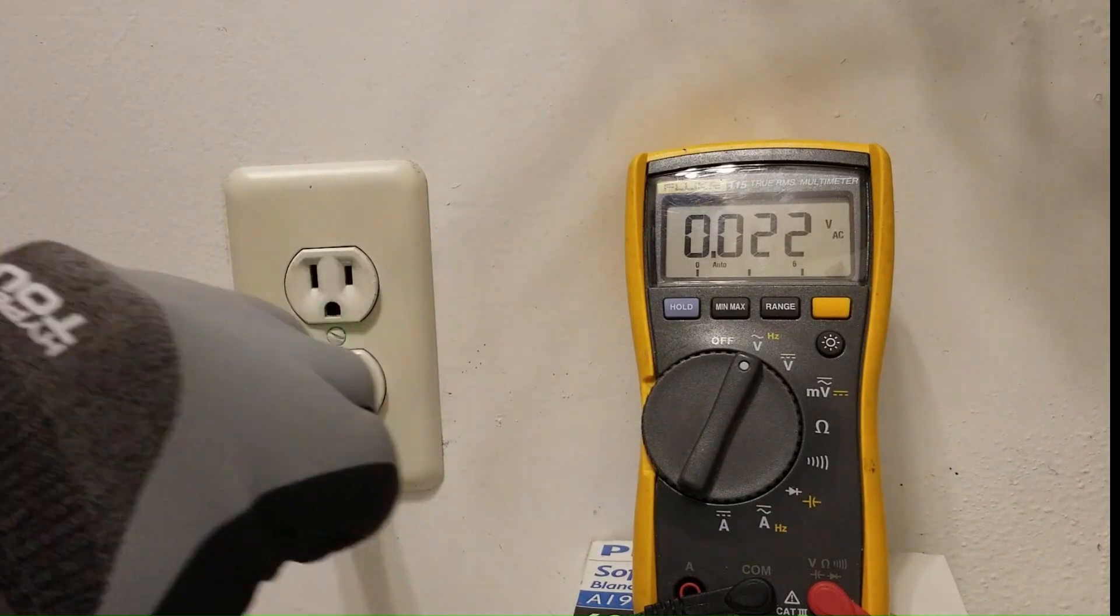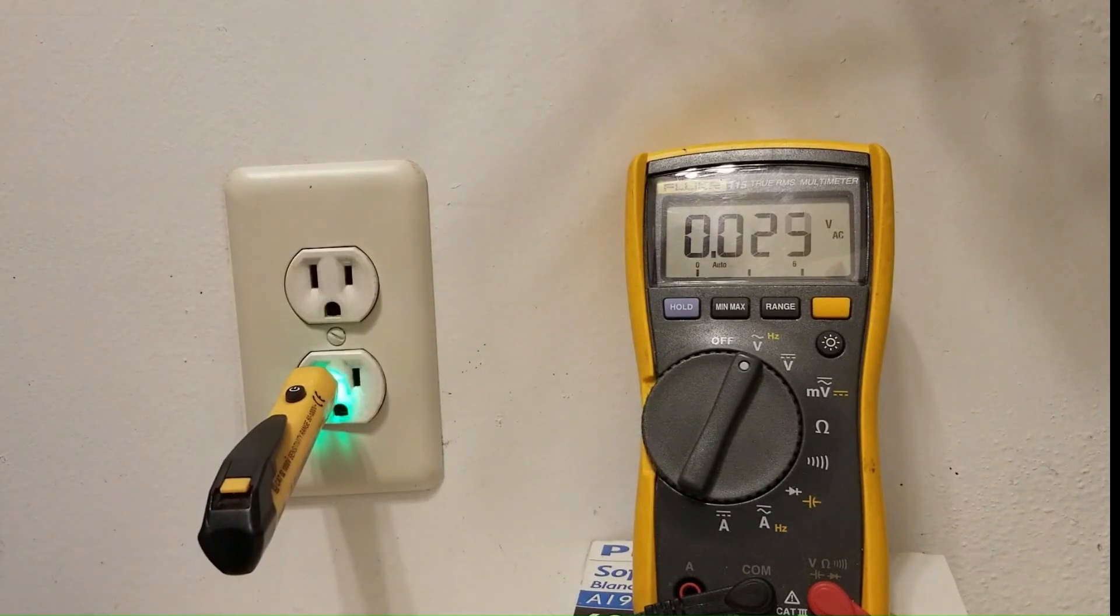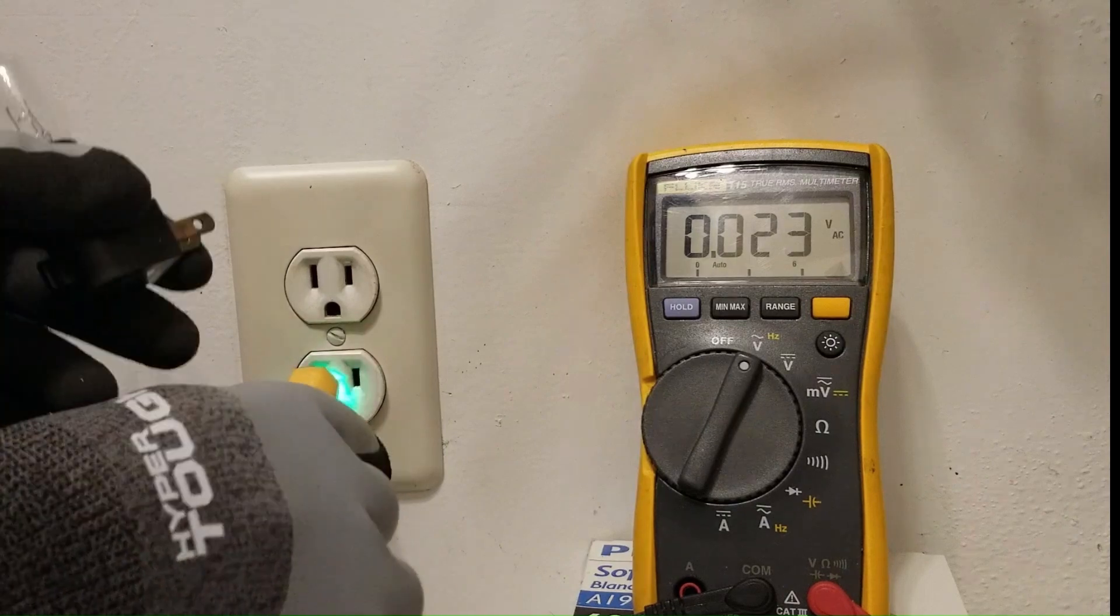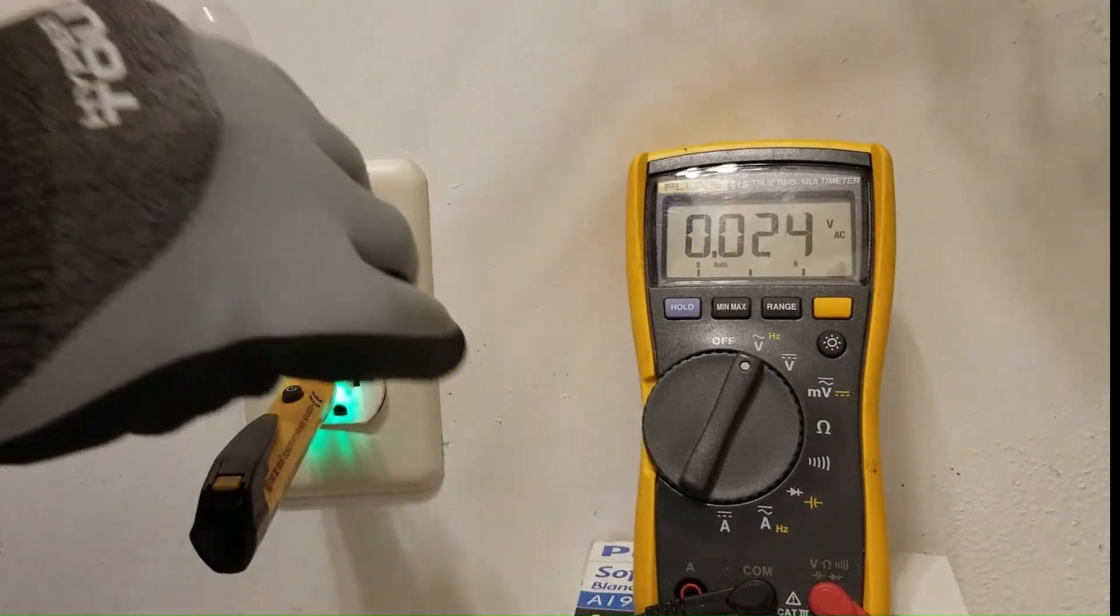So if that's the case this should signal on the neutral side when I put the load in. If that's the case that tells us we have a floating neutral.